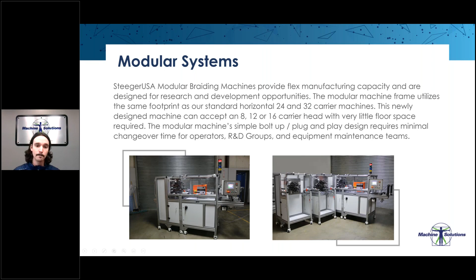In the catheter world, most customers start the production of braiding catheters with a 16 carrier braid machine in the 1x2 or 1x2x2 pattern, because it has the fastest throughput and has all the characteristics needed, to a limit. What I mean is the full regular pattern does have radial force strength and compression strength, just maybe not as good as the half load diamond pattern or the full load diamond.